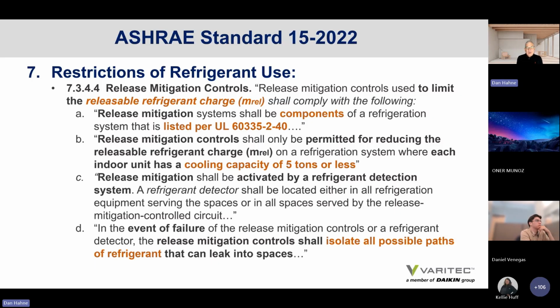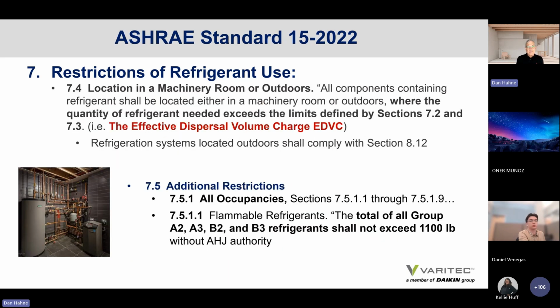And some ducted variable refrigerant indoor fan coils have greater tonnage capabilities. So just be aware of that. Release mitigation shall be activated by a refrigerant detection system. The use of refrigerant detection systems are now going to be used in the standard to help safety shutoff valves respond when there's a refrigerant leak and shut off refrigerant circuits. So in the event of a failure of the release mitigation controls or a refrigerant detector, the release mitigation controls shall isolate all possible paths of refrigerant that can leak into spaces.